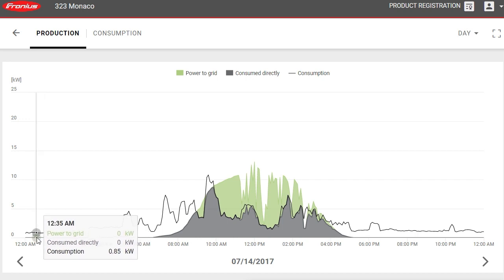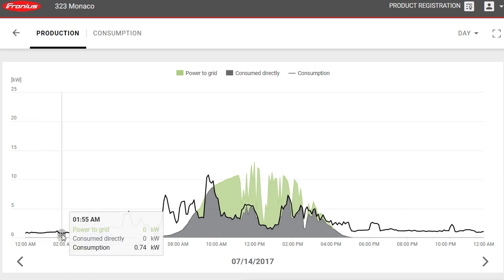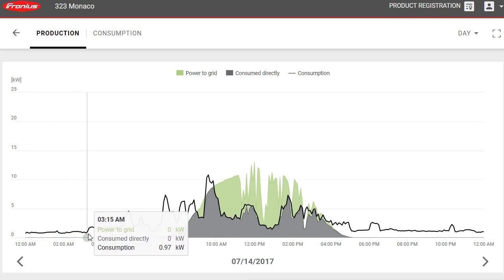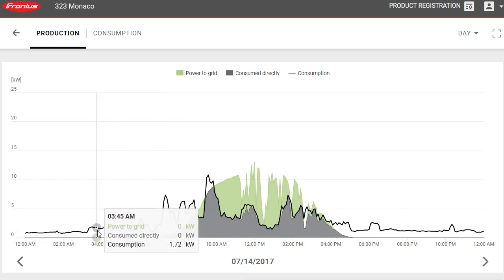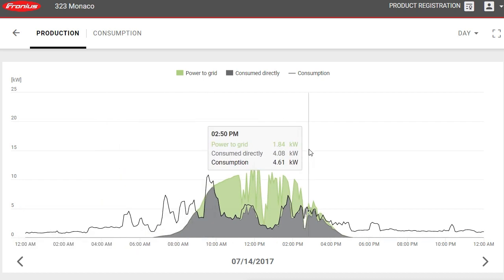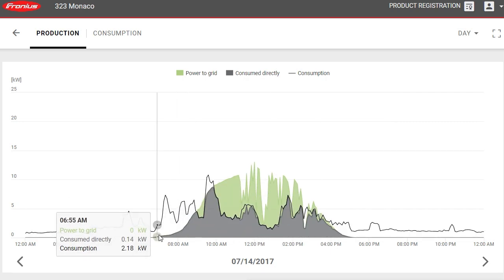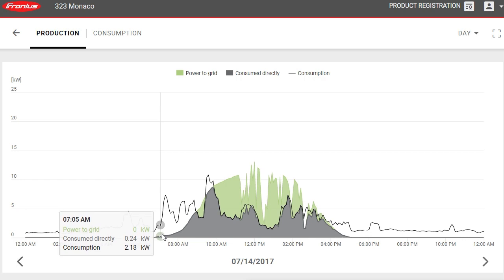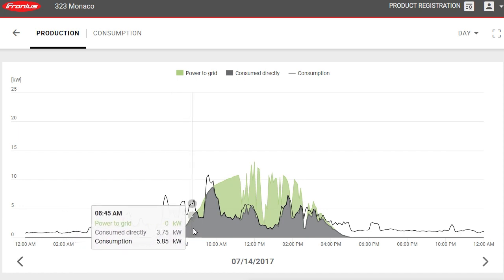The black line represents the consumption of the property. Just after midnight at 1am, we're looking at a standby load of just under a kilowatt - around 800 to 900 watts. At 4am it jumps up to about 1.6 kilowatts. Then around 7am the solar starts coming on board, and we can see the power consumed directly from the solar panels. At this point, consumption is 2.18 kilowatts with 0.24 kilowatts coming from solar.